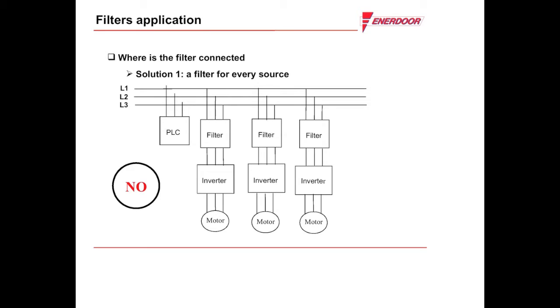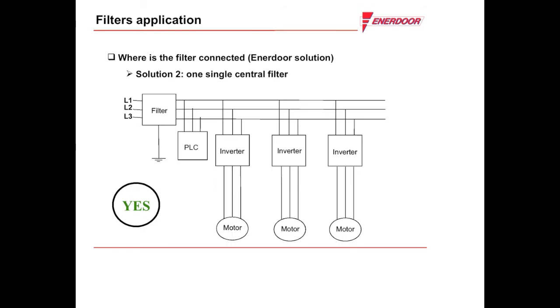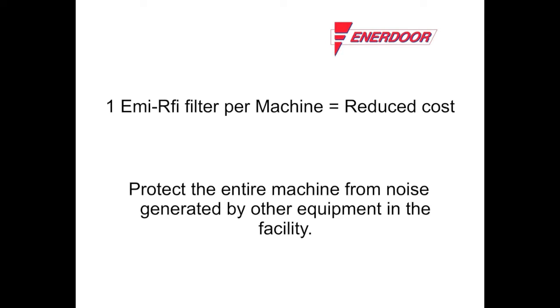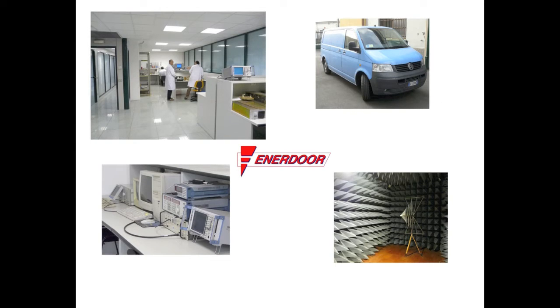Many OEMs use one filter for every drive, which can be costly to purchase and install. Enerdoor's strategy is to use only one filter per machine, located after the main switch. This reduces cost and protects the entire machine from the noise generated by the drives, as well as the noise that could be coming from the main line of the facility.